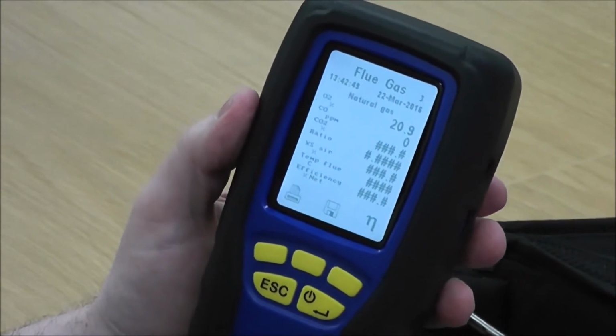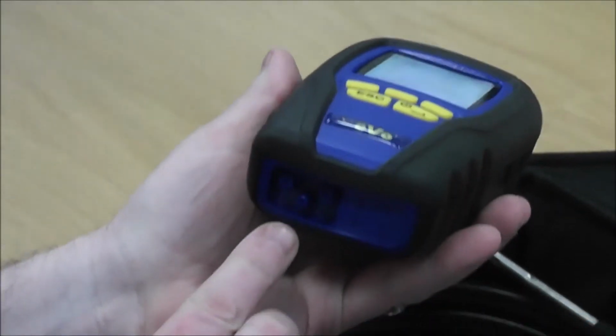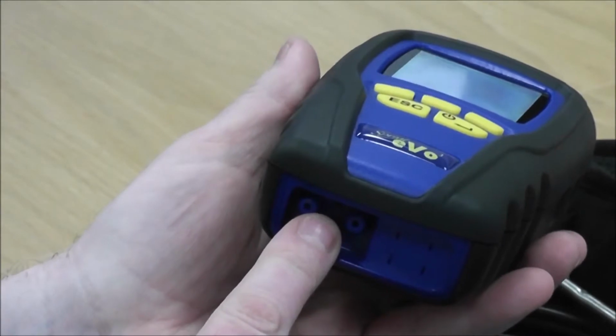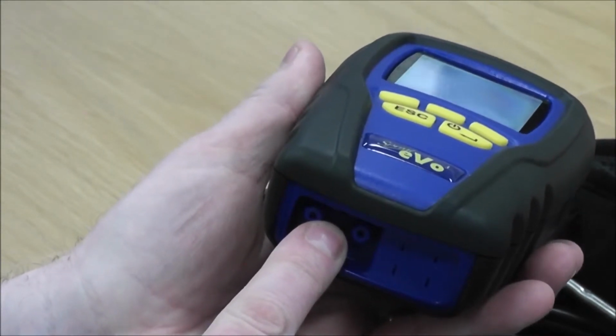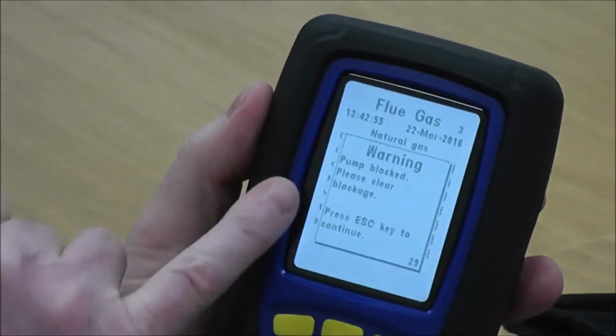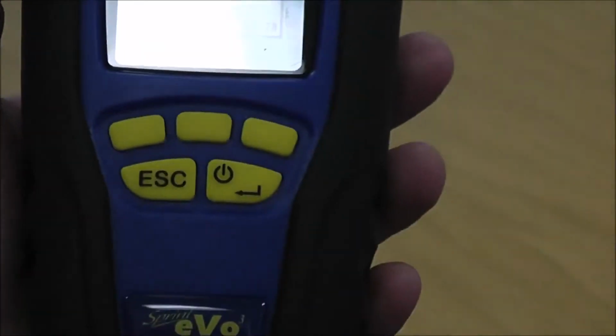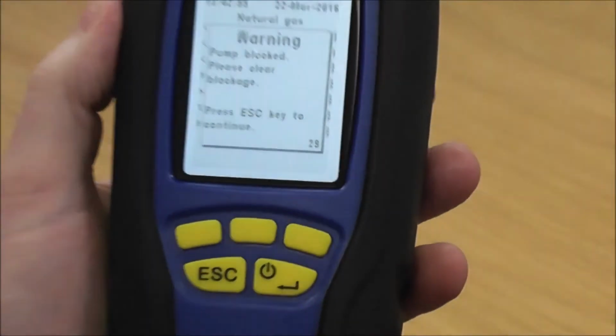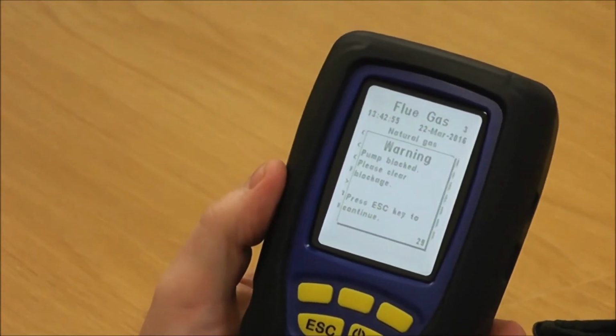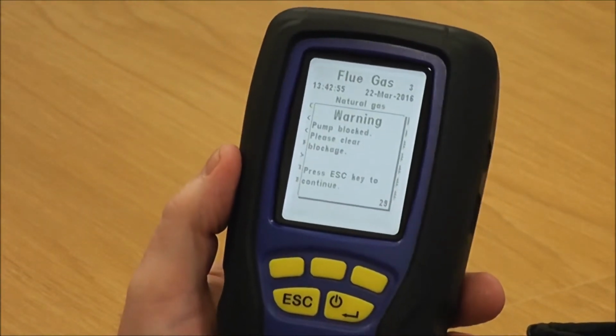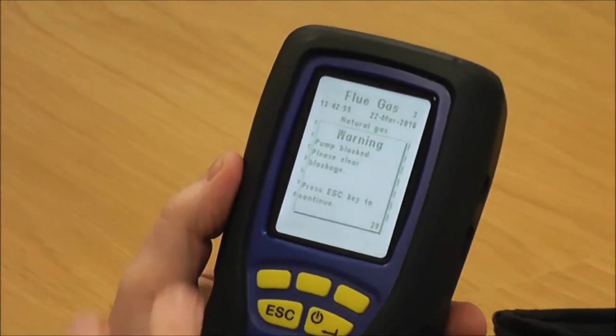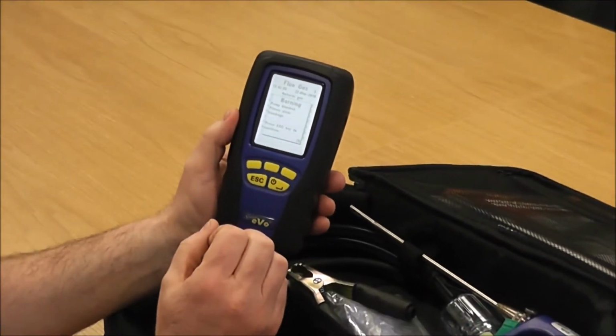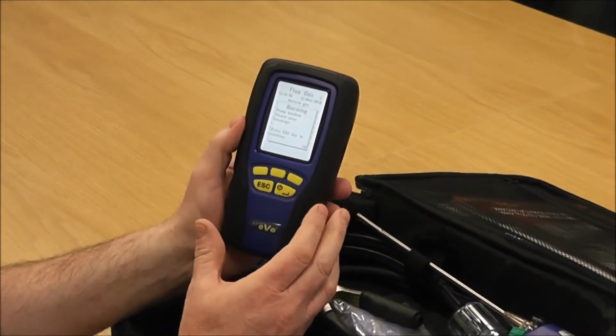Now the other thing you can do is if you block up the middle spigot underneath, completely block it, what happens is it comes up with pump blocked. Now that's obviously put in place to protect from the flue probe sucking up moisture into your analyzer, or if you've got a blocked filter, it also identifies that for you. And it's to protect the analyzer. But what we're actually using it for on this particular test is to make sure there's no internal tube leaks, or that the pump's got any blockages or debris in it.